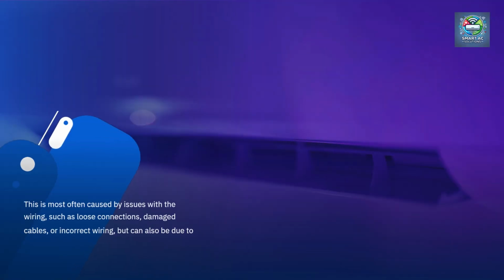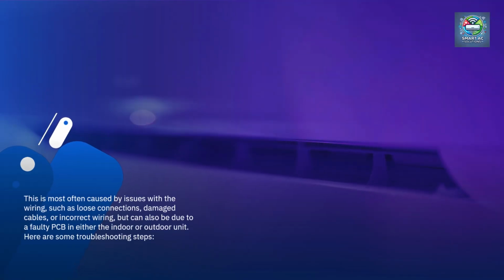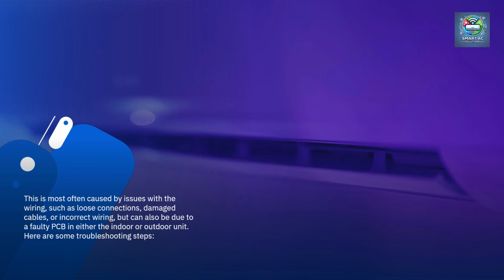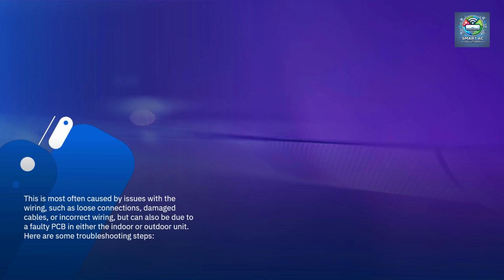This is most often caused by issues with the wiring, such as loose connections, damaged cables, or incorrect wiring, but can also be due to a faulty PCB in either the indoor or outdoor unit. Here are some troubleshooting steps.